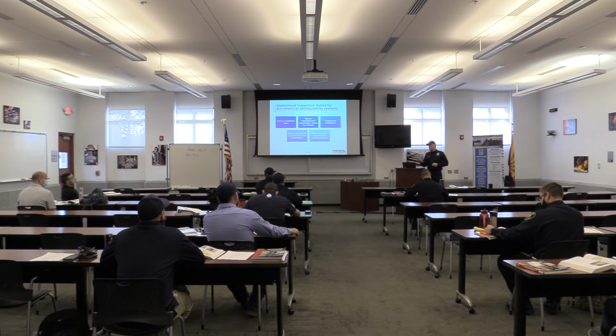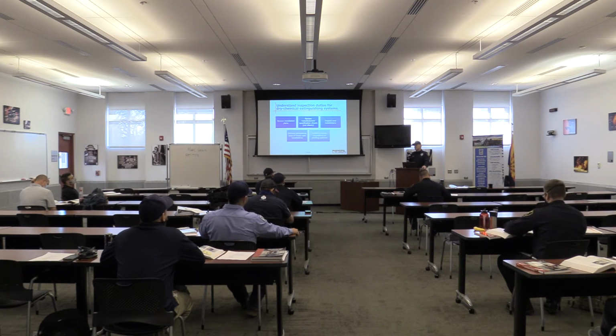A kitchen that operates daily, say 8 in the morning to 9 p.m., maybe every 6 months. A 24-hour a day operation, the NFPA standard may require inspections every 3 months. A restaurant with a wood-fired stove is required to be inspected, tested, and cleaned every month. So it's just based on the type of use.